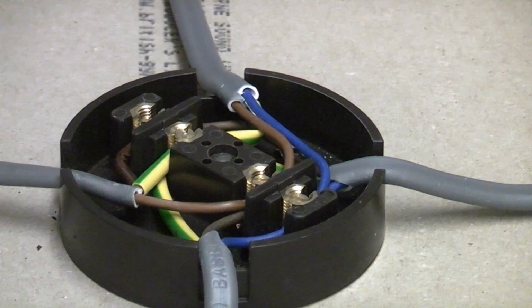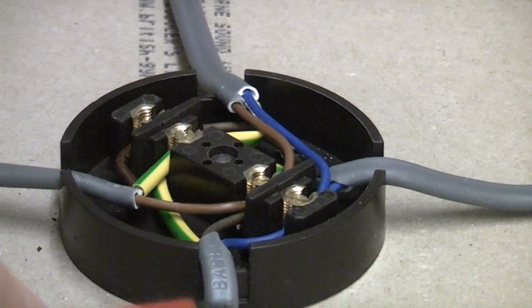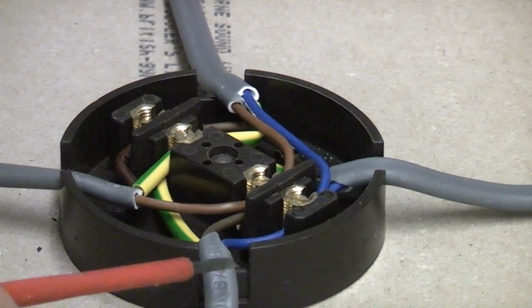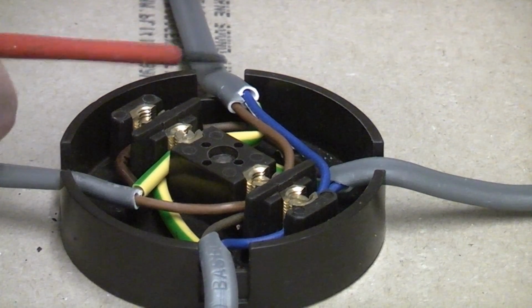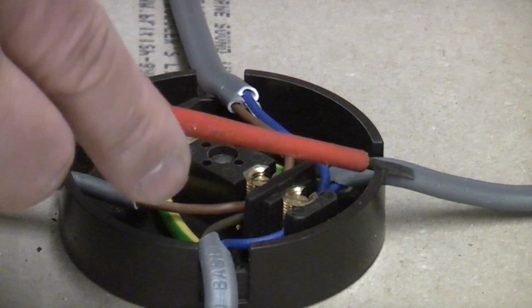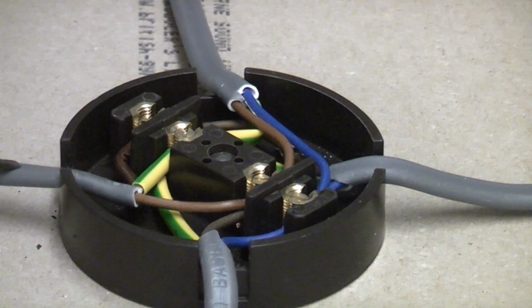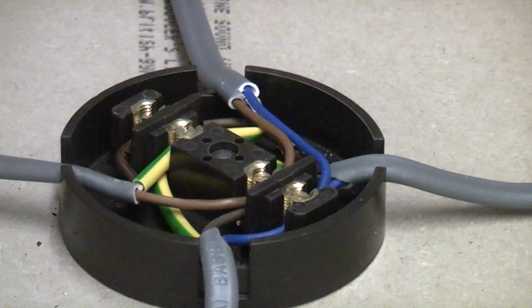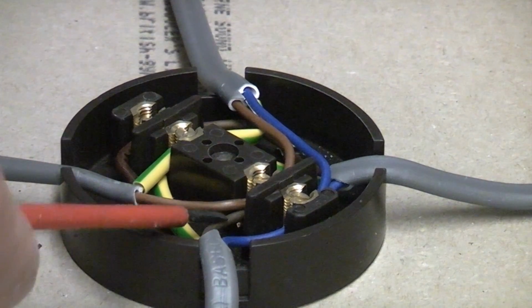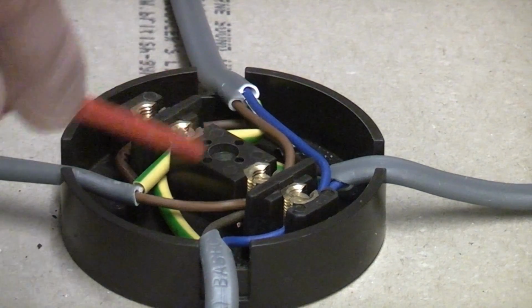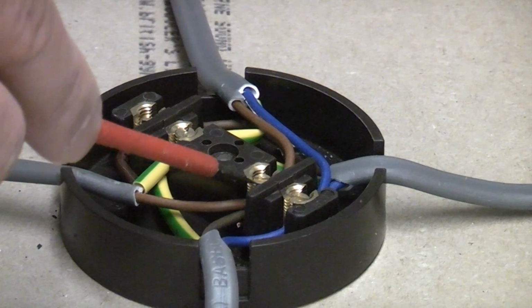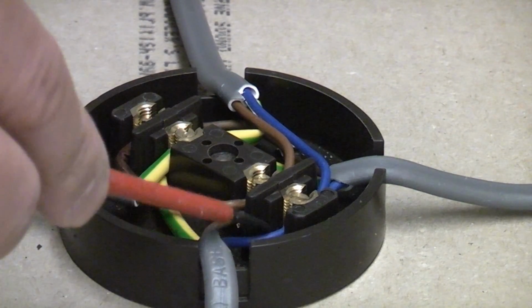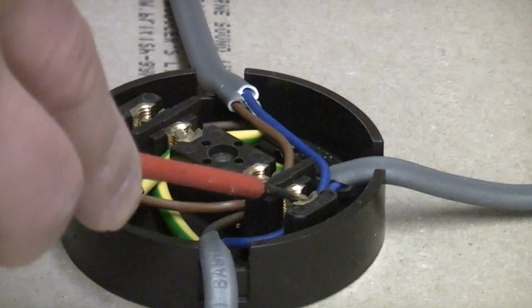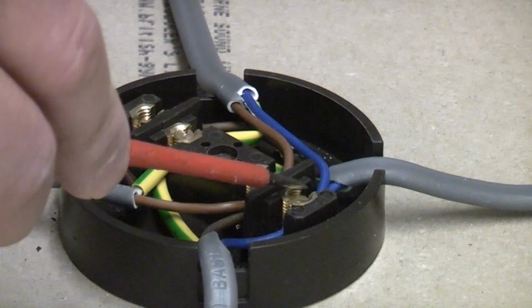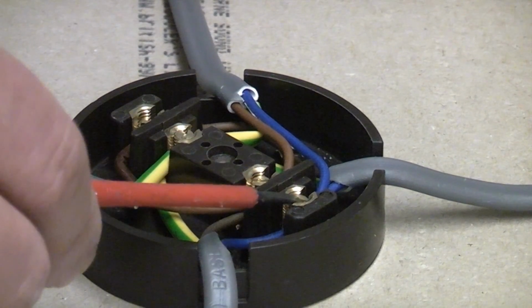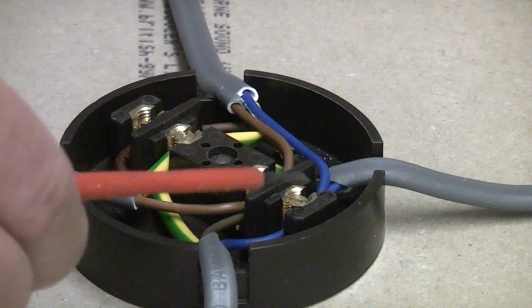I'll just briefly explain to you about the ceiling rose. This cable here is the circuit cable, so is that one. This is the cable that's actually going down to the light, and this is the cable that's going to the light switch. So if we're looking there, we can see that we've got 3 brown wires going into that terminal, so that is the permanent live, and we've got 3 wires going into the neutral terminal, so that is the permanent neutral. So we need to take up a supply of each one of those.